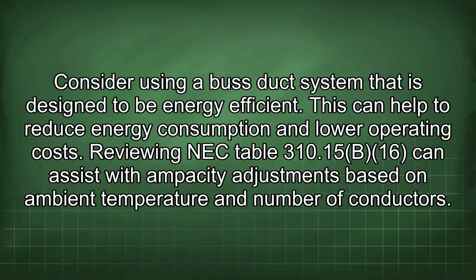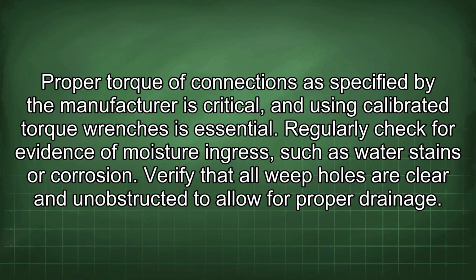Consider using a bus duct system that is designed to be energy efficient. This can help to reduce energy consumption and lower operating costs. Reviewing NEC Table 310.15(B)(16) can assist with ampacity adjustments based on ambient temperature and number of conductors. Proper torque of connections as specified by the manufacturer is critical, and using calibrated torque wrenches is essential.